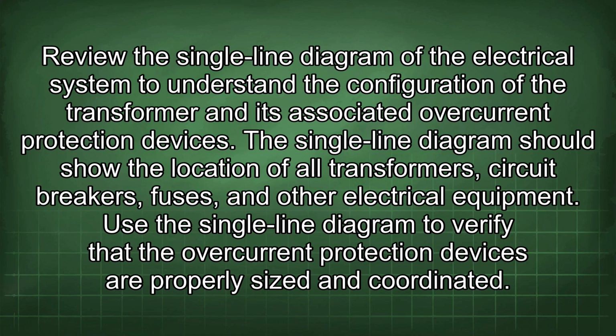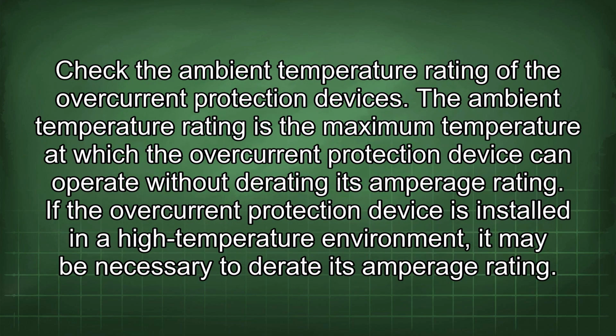Review the single-line diagram of the electrical system to understand the configuration of the transformer and its associated overcurrent protection devices. The single-line diagram should show the location of all transformers, circuit breakers, fuses, and other electrical equipment. Use the single-line diagram to verify that the overcurrent protection devices are properly sized and coordinated. Check the ambient temperature rating of the overcurrent protection devices.